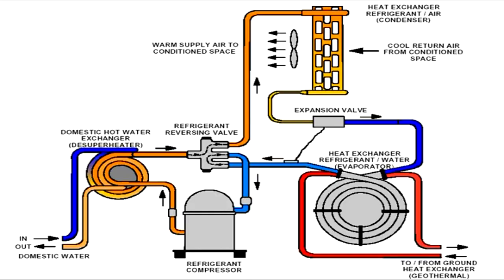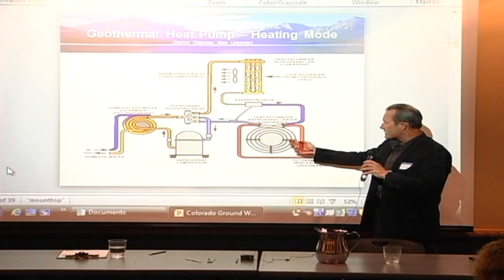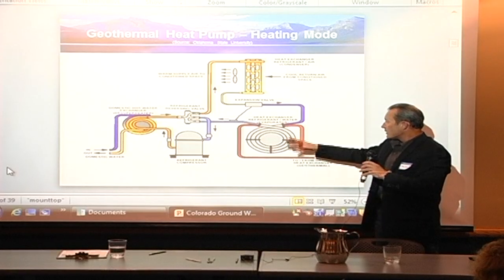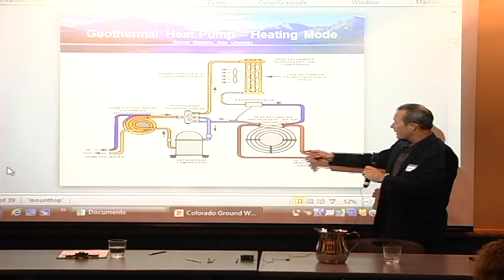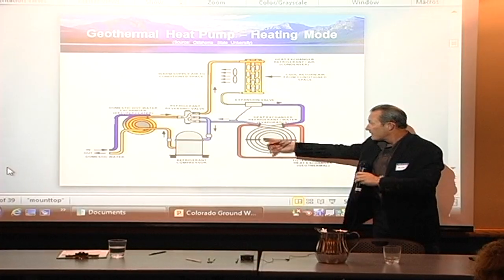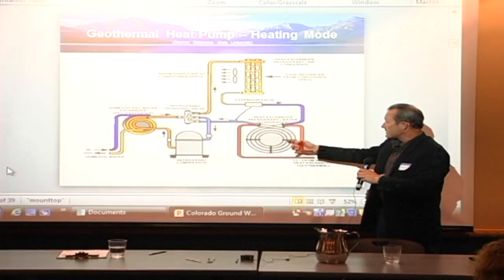This one will probably be easier for me to stand up and point out, but again, this is very simply how a heat pump works. This is in the heating mode. I'll show you some pictures, but I have all this plastic pipe buried in the ground, and it's coming in as the red fluid here. That fluid is typically a mixture of propylene glycol and water. The water comes in at approximately 50 degrees, we'll use for example, and goes into a pipe heat exchanger. On the outside of the pipe, we have 50-degree water flowing through. On the inside is refrigerant.